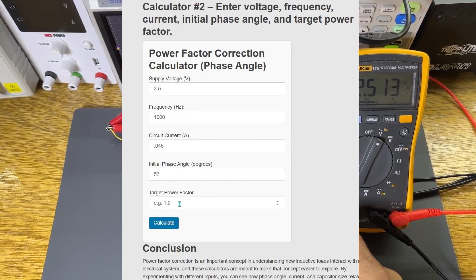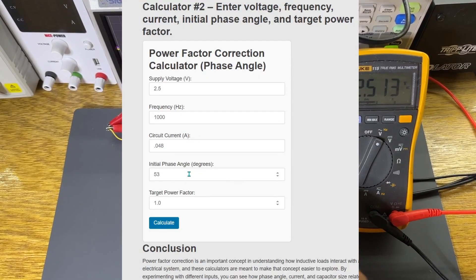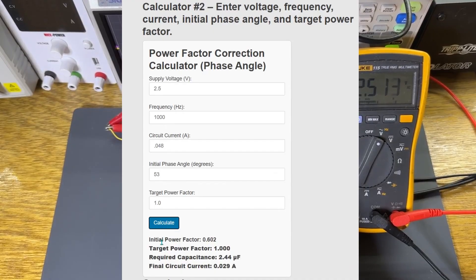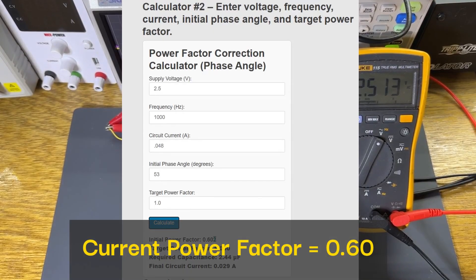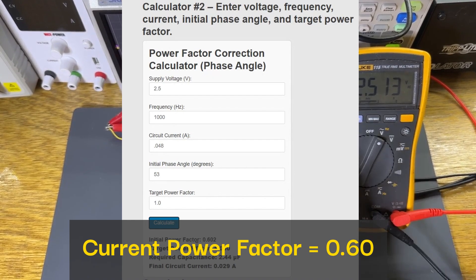And our target power factor, of course, we want that to be 1.0, which is perfect. So here's the output of our calculator, which indicates that our power factor is 0.60, which means we're only using 60 percent of the power that we're pulling from the supply effectively.